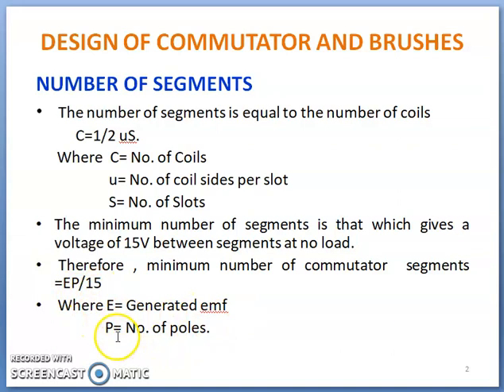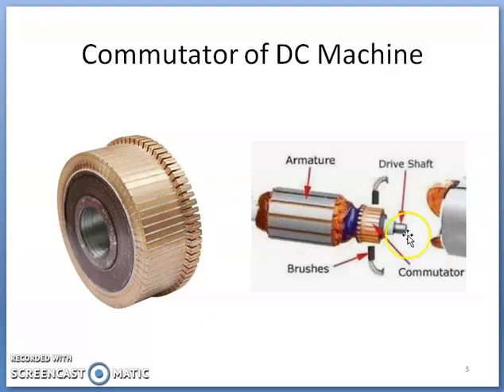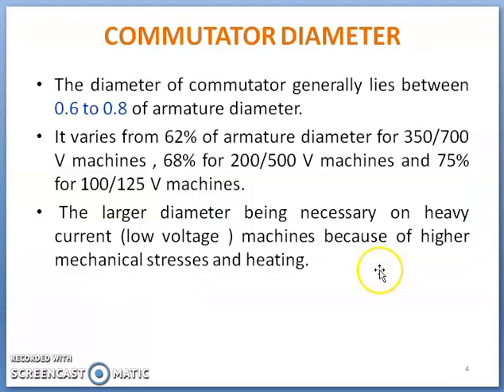The minimum number of commutator segments is taken as EP divided by 15, where E is the generated EMF and P is the number of poles. Between two commutator segments, mica is used as insulation material. The commutator is fixed at one end of the armature, and brushes are used to supply current to the external circuit — current is collected from the rotating commutator via the brushes.